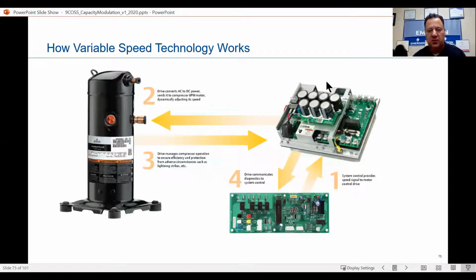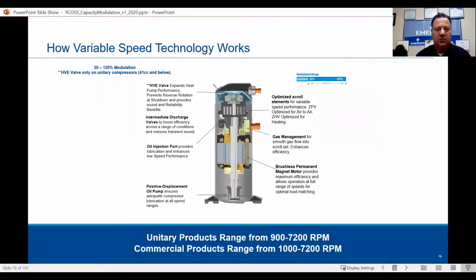So again, how this works is we have our controller. Okay, system controls provide speed signal for the motor controller, which sends it on to the compressor. Drive converts AC to DC power, sends it to the compressor. The brushless permanent magnet motor dynamically adjusts its speed, back to the drive and sending it back to the controller once again. Drive communicates diagnostics to system control. How variable speed technology works, I'm not going to beat this up. We kind of went through that already. I stuck some slides in there on a presentation I have where I'm teaching inverter technology. So I use those at the beginning. Not going to beat that up a whole bunch there.